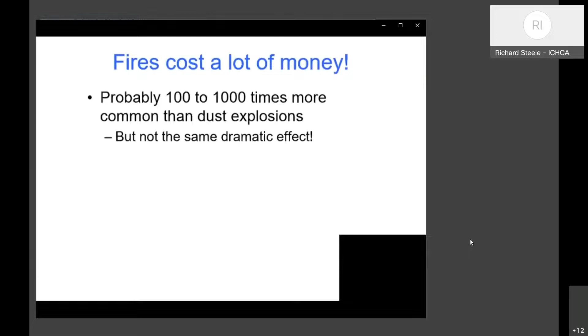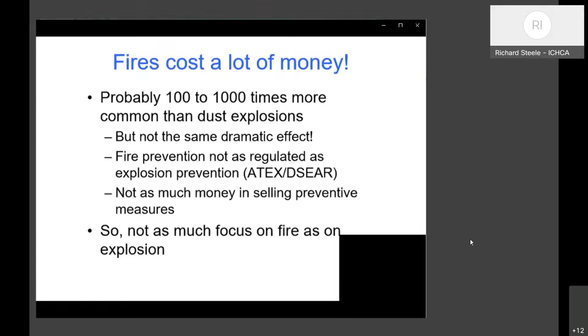It's necessary to prepare for when things go wrong, because they will. If you're handling combustible material with dust in it, sooner or later you'll get fires and/or explosions, and you need to be ready. Don't rely on the fire brigade—by and large they'll come in, do things wrong, and make matters worse. So you must have your own methods and procedures for fire management. Fires are actually much more common than explosions and cost a lot more money overall, even though they're less dramatic. You might see one dust explosion in your lifetime, but you'll see quite a few fires working in this area. There's not as much money in selling preventive measures for fires as for explosions, because everyone knows how devastating an explosion can be. So there isn't as much focus, but you need to put that focus on.